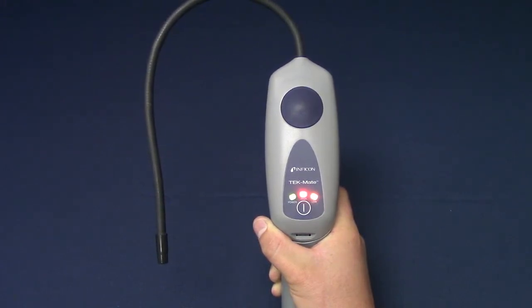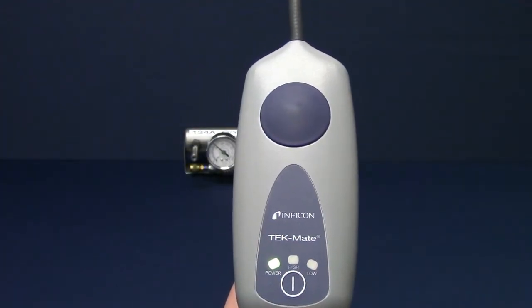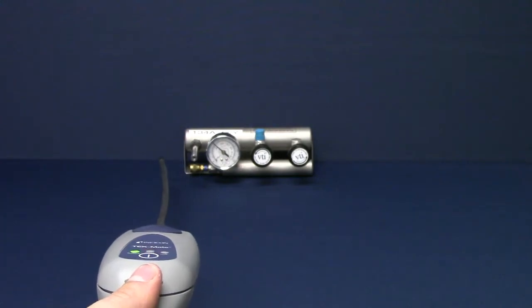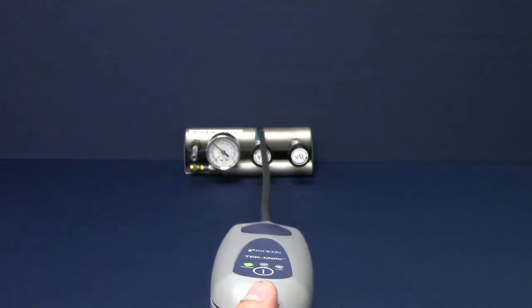TEK-Mate always starts in high sensitivity. This mode is useful for finding the general source of the leak. Begin by moving the probe slowly around the suspected leak area. TEK-Mate will beep faster the closer it is to the leak until a continuous beep is heard. Move the probe away from the suspected leak for a few moments and repeat to verify the leak.